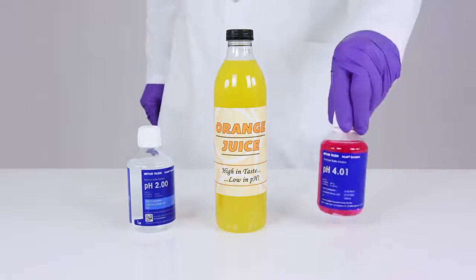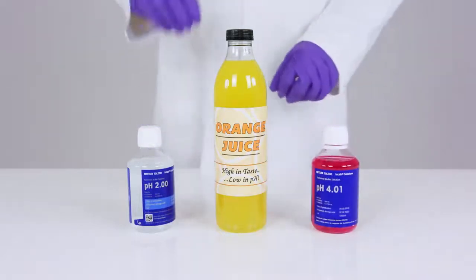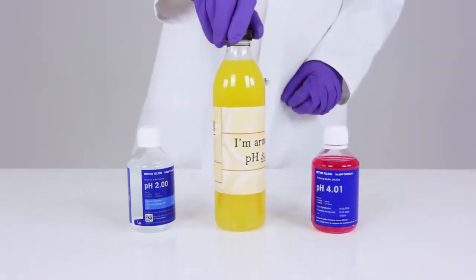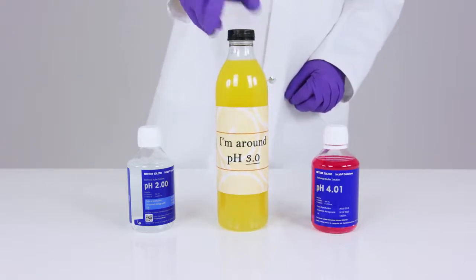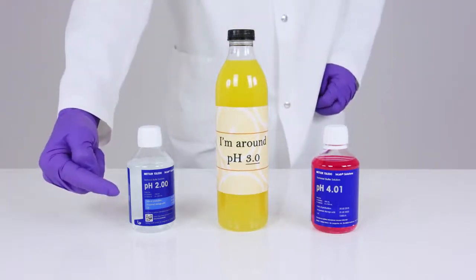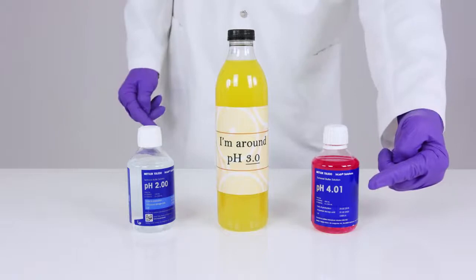It's recommended that the difference does not exceed 4 pH units. So, for example, if you were measuring some nice fresh orange juice, which is about pH 3, then you would bracket with buffers pH 2 and pH 4.01 for best results.